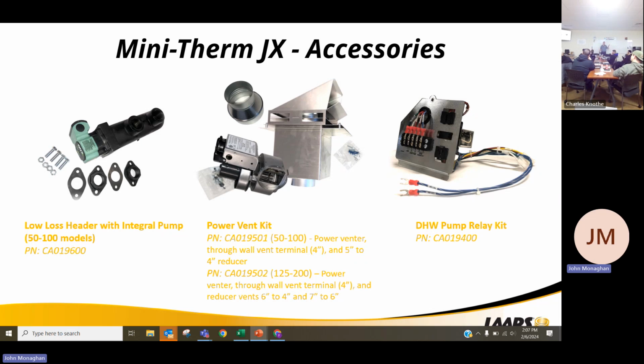Other portion with this, it can also be power vented. One of the advantages of this over your sidewall vented cast iron boilers, if you buy a cast iron boiler that has the fan already built into it, you have to run that gasketed stainless steel vent pipe all the way to the outside. So if we're buying the kit with this and it wires right in, you don't have to get all creative. It's not like buying a Carlin or a Fields kit where you have to figure out how to wire everything. This is designed for this boiler, so it's very easy for you to wire in.